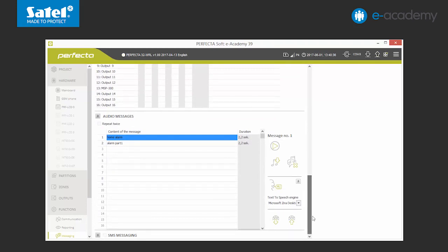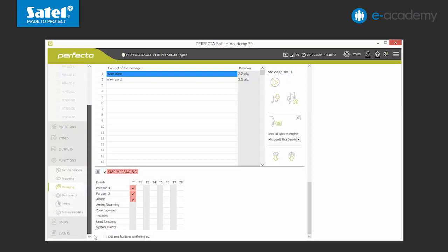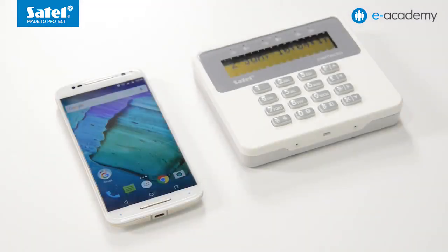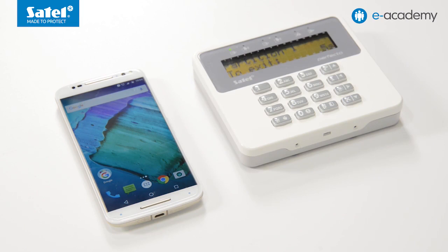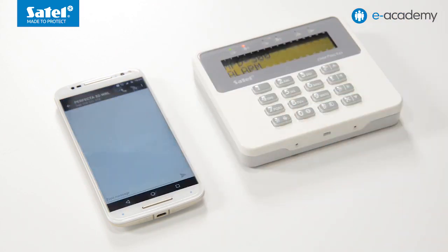We can also use the second type of notification, that is SMS messages. We unfold the SMS notifications list. Firstly, we choose the partitions in the chart. The content of messages is downloaded from the list of events. After the data is sent to the control panel, we will check how SMS notification works. For this purpose, we will arm partition 1 and trigger an alarm there. As you can see, the notification has worked as set.